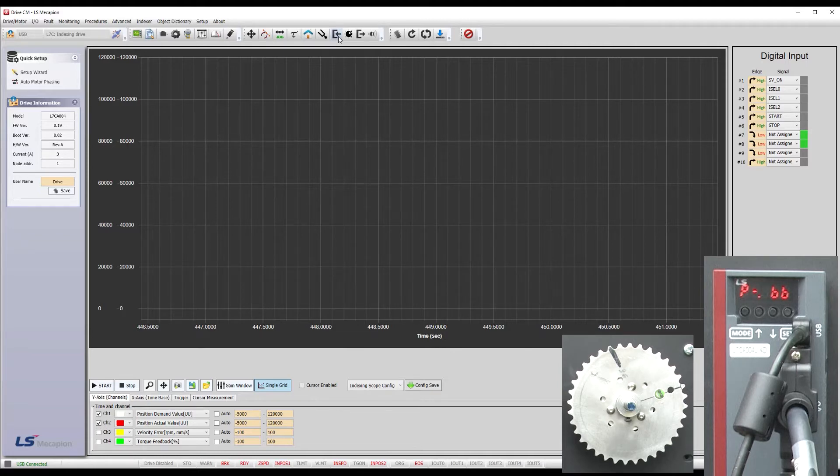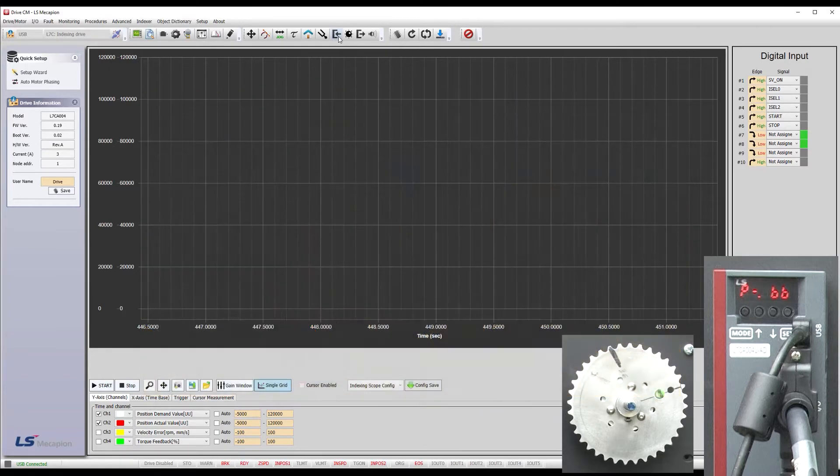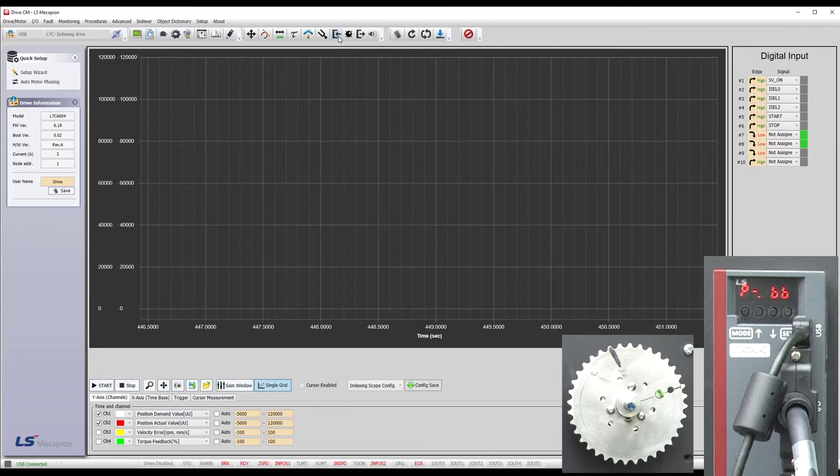OK, all we've done so far is set up a motion profile using indexing. Again, we cover all of this in this video on the indexing mode. Now that we've done that, we can finally talk about online auto tuning. We just did a factory reset, so this drive has not been tuned yet, so let's see how it performs out of the box with this load.